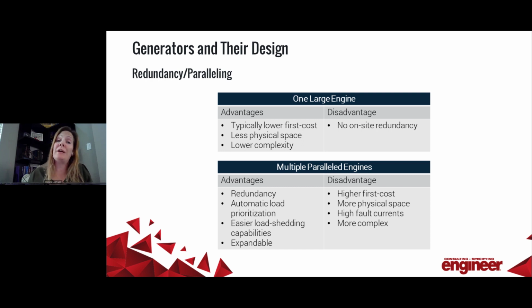So contrarily, a parallel system provides advantages since it does provide that on-site redundancy. Other advantages include more ways for that load prioritization and shedding with the different step loads that we discussed earlier. It's also more easily expanded, providing future flexibility. However, the drawbacks include an inherent higher first cost. You're buying more equipment, you need more physical space, and it's overall a more complex system. Also, paralleling multiple generators produces higher fault currents onto the distribution system. That's kind of an entire other webinar in its own.